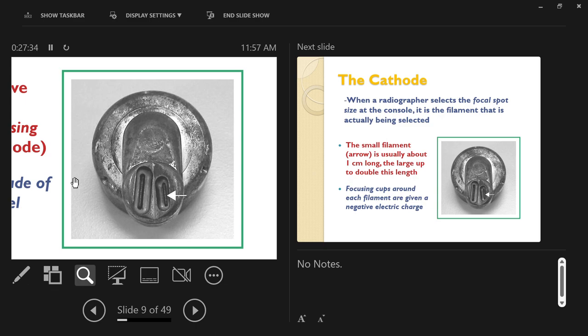Detail on images will change when moving from small filament to large filament — it has to do with the size of the area from which x-rays originate. You consider two things: how much detail you want, and how many x-rays you're producing. Conveniently, the equipment does a good job of selecting the right filament for you, but you can override it.